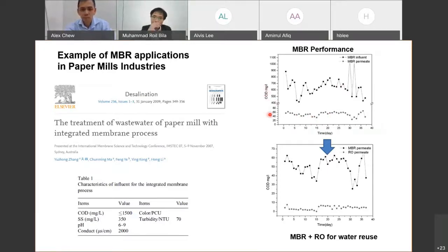And in this study, they not only treat the wastewater, they also reuse it for the process. You see here, the graph is exactly the same as here. They use the MBR effluent as a feed directly to RO, and by using RO, it can reduce the COD below 10. Okay, this is an example for the paper mill industry.